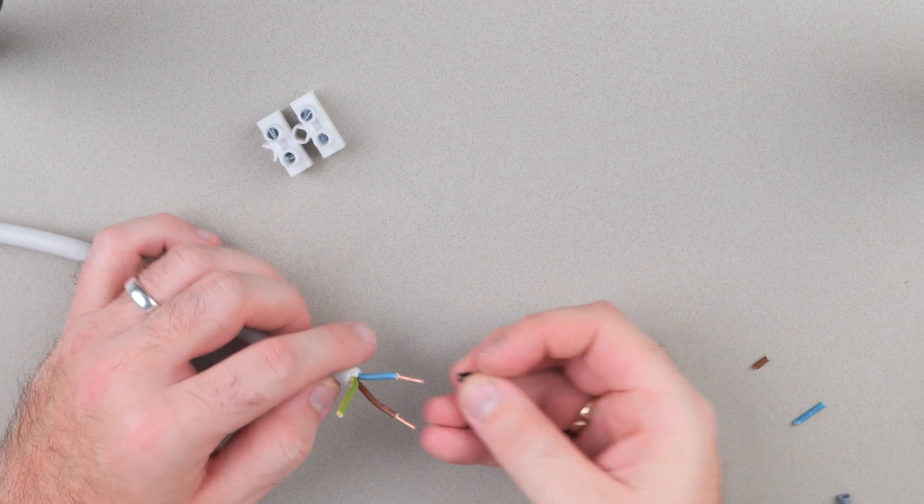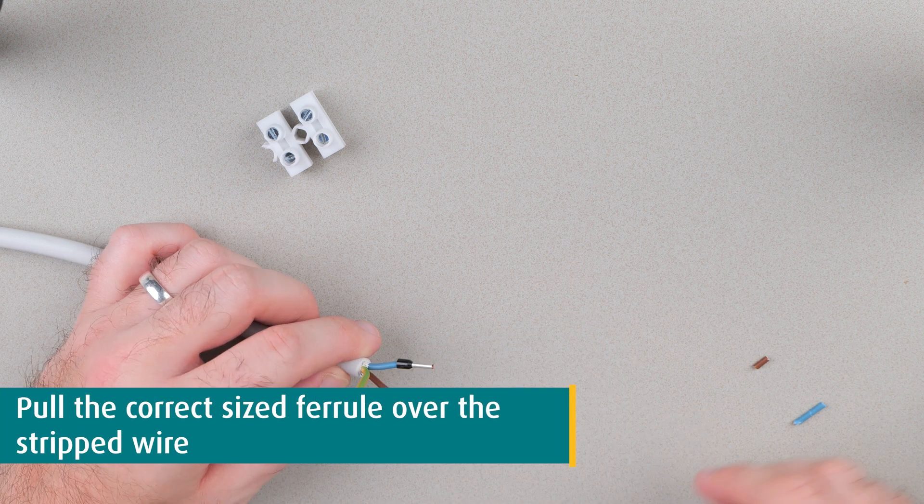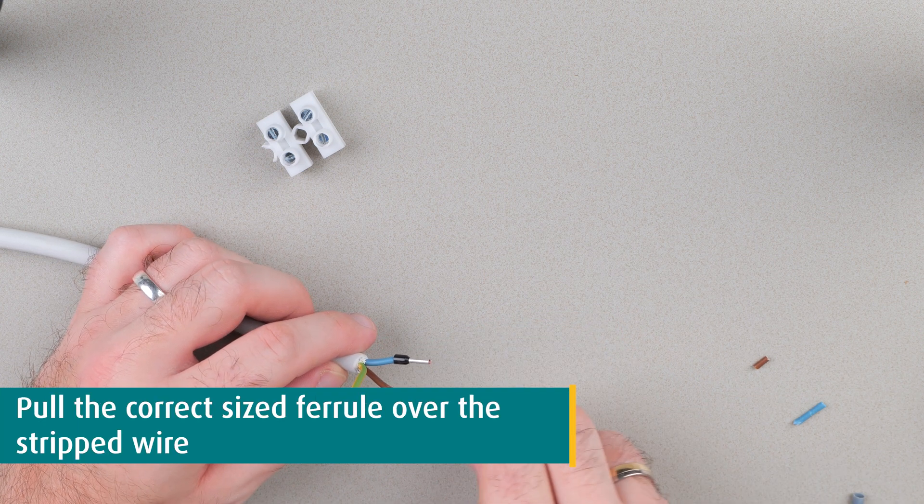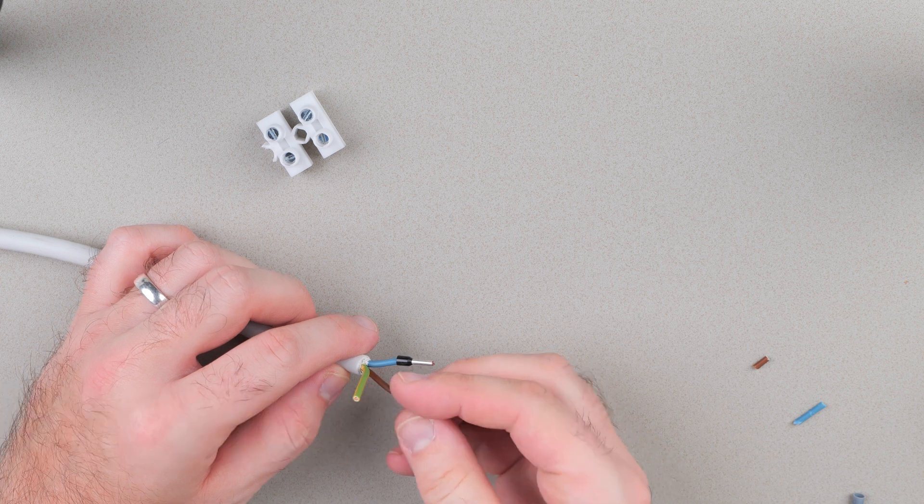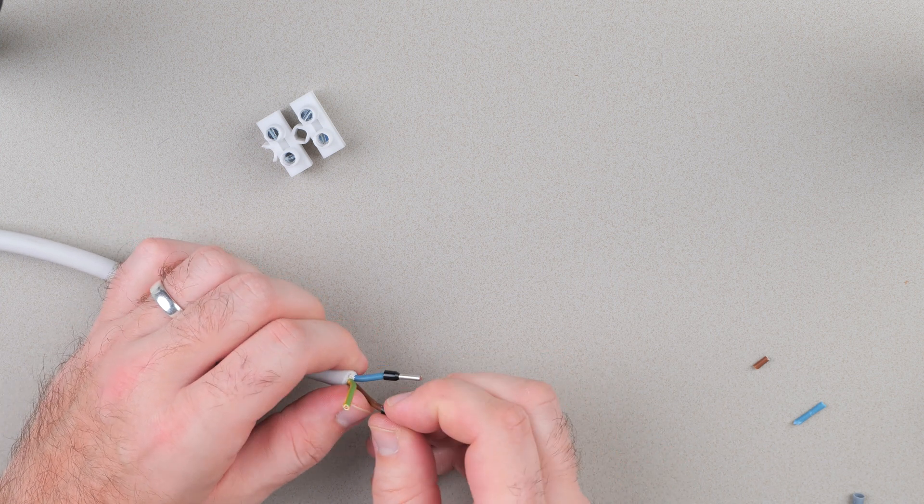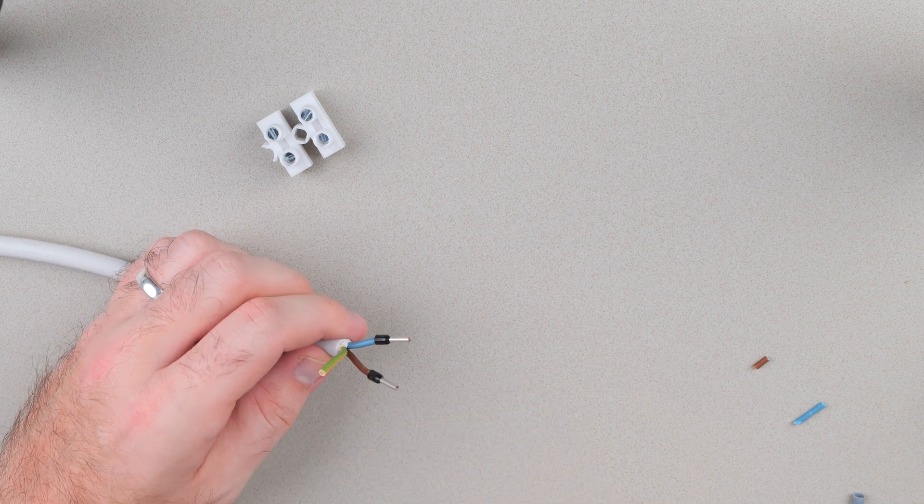Pull the ferrule over the wires so the stripped wires have contact to the conductive metal of the ferrule. Do not twist the wires because this will change the cross section and may damage them. Best is to just make sure that they are all straight.